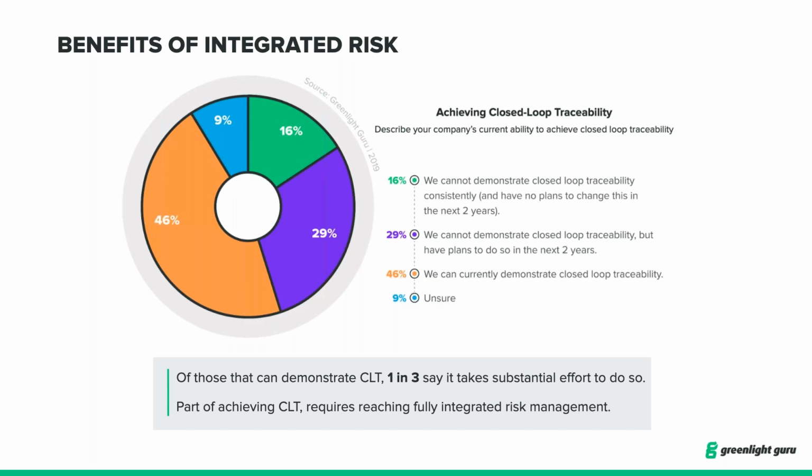Basically, I want to make sure that this is a control system, if you will, that I have these feedback channels going back into our risk management process, and then we follow the methodology that we have to hopefully define within our processes and procedures that align with 14971 about analyzing, evaluating, controlling, mitigating risk. So this is really important, this concept of closed loop traceability.